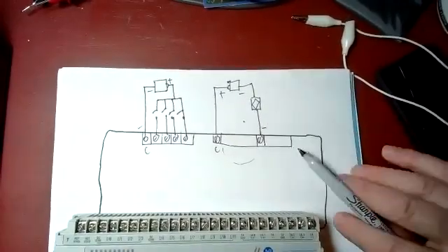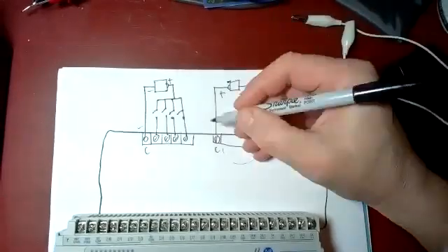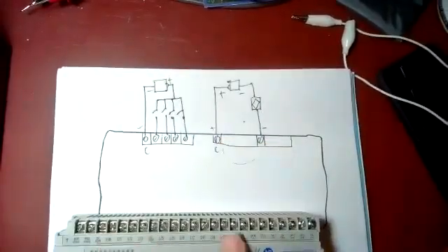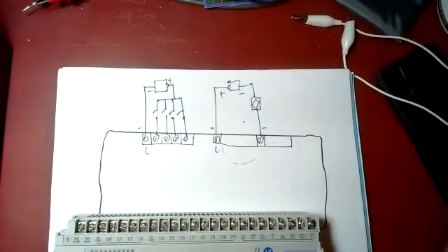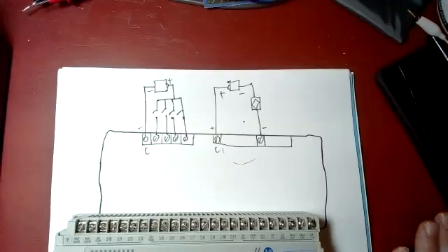So there are cases where I want to run up that common. It's either wired to the plus or it's wired to the minus. And by having two separate commons and you split your input rail, I can set up this PLC with either style of sensors when I'm wiring up different kinds of sensors.